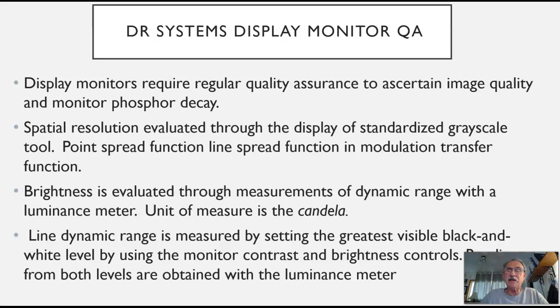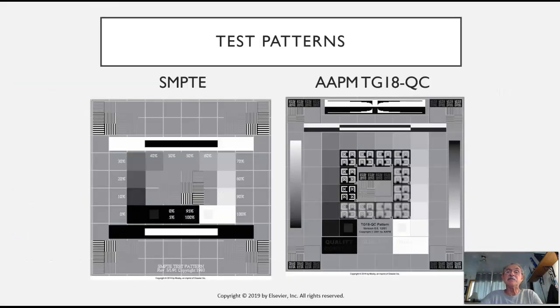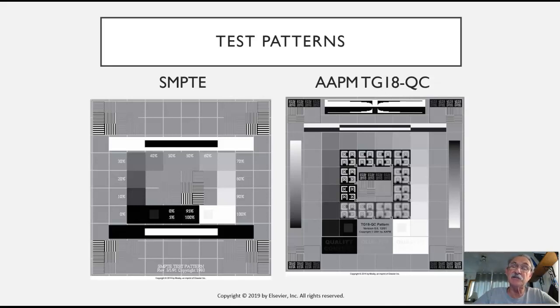The dynamic range is measured by setting the greatest visible black and white level using the monitor contrast and brightness controls, and readings from both levels are obtained with the luminance meter. Here are a couple of test patterns we would bring up on our monitor. The first is produced by the Society of Motion Picture and Television Engineers — SMPTE. The other is a test pattern from the American Association of Physicists in Medicine — AAPM. These are both standard test patterns used for this kind of evaluation.